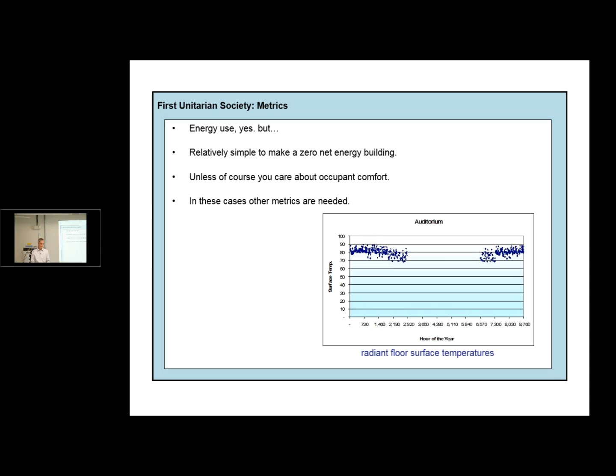One of the concerns was that because we had below grade zones and some above grade zones, whether this radiant floor we were considering was going to make surface temperatures uncomfortably hot, radiant temperatures uncomfortably hot. So one of the metrics we looked at was the surface temperature of these floors on a minute by minute, hour by hour basis throughout the entire year. Again, the flexibility of a tool that doesn't give you canned output reports was an advantage in this particular case.